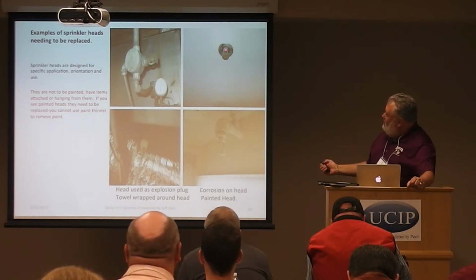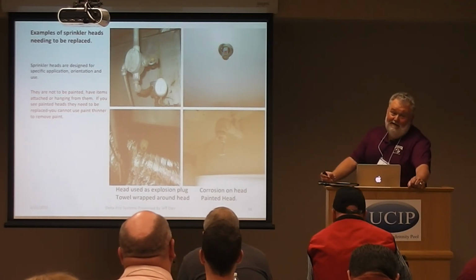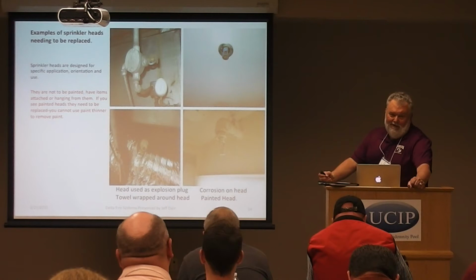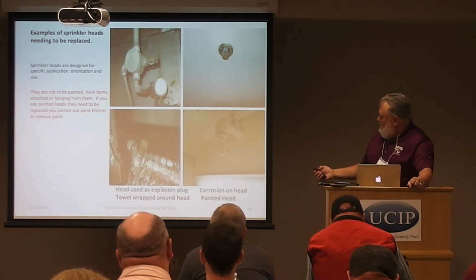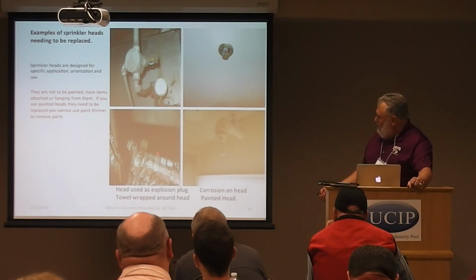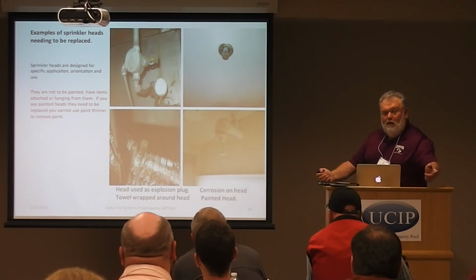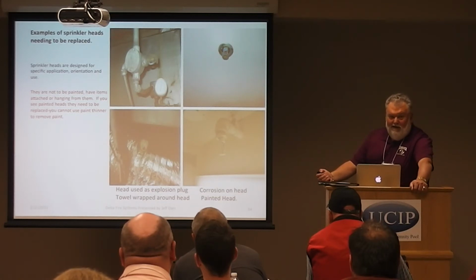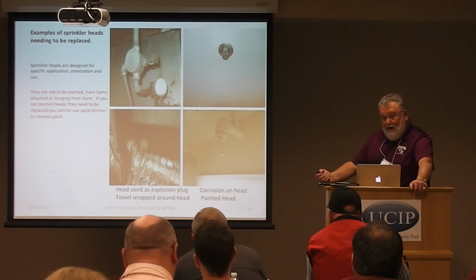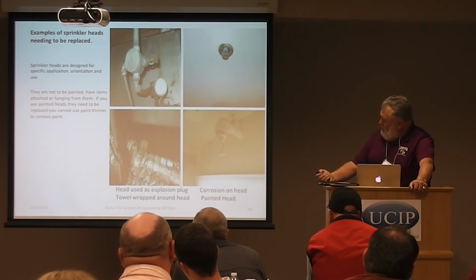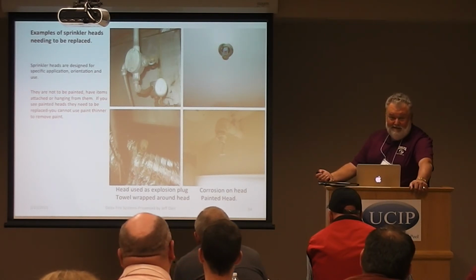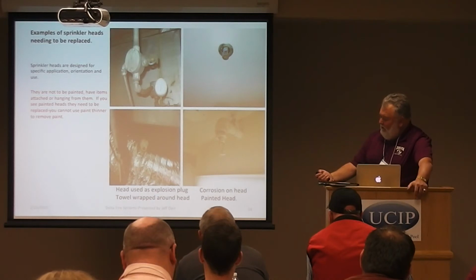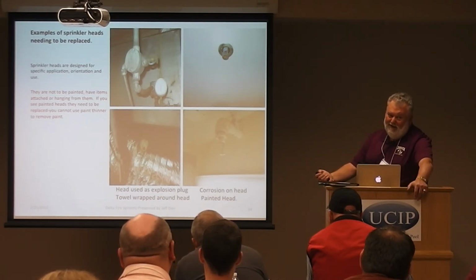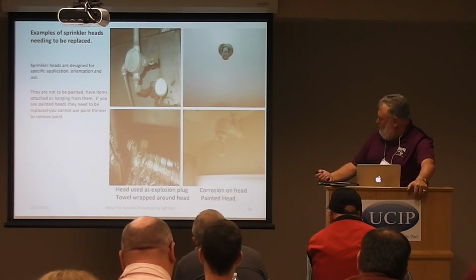This head right here, you can see all the green and blue on that. That head, all the corrosion, that head needs to be replaced. That's a time bomb waiting to go off right there. And this one here, I get a kick out of. That's a bathrobe strap is the only thing I can equate it to, wrapped around that sprinkler head. I don't know if they're trying to keep the head warm, trying to keep it away from that duct, or exactly what they're doing. That may have been rattling at one time. But first of all, the head doesn't meet the code requirement because of the discharge blockage right there. But then to wrap that around is really funny.